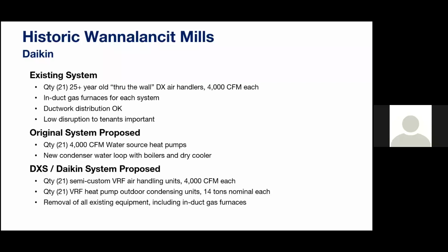Now, looking at what we faced initially when we were brought into the project, there were originally 21 very old DX air handlers, all around 4,000 CFM, so pretty big units. There were then gas furnaces for each system inside the duct downstream of the air handling units to handle the heating. So these units were having all sorts of issues with compressors failing and limited cooling capacity, with the equipment being towards the end of their usable life. So the owners knew they needed a new system.